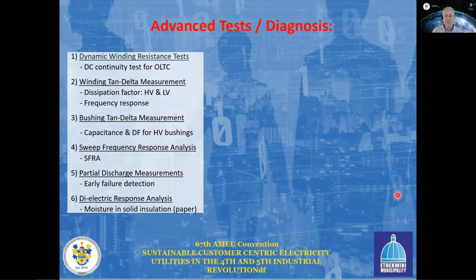The first one being the dynamic winding resistance test, which is in essence also a DC test, similar to the static winding resistance test that we did earlier under the standard tests. But in this case, we are measuring for continuity between tap positions, from tap 1 to tap 2, for instance. We want to ensure that our tap changer doesn't have any interruptions in the selector switches or the diverter switches from one tap to the next. It is very important that this test is done for all tap transitions, tapping up and tapping down, as well as for all phases.